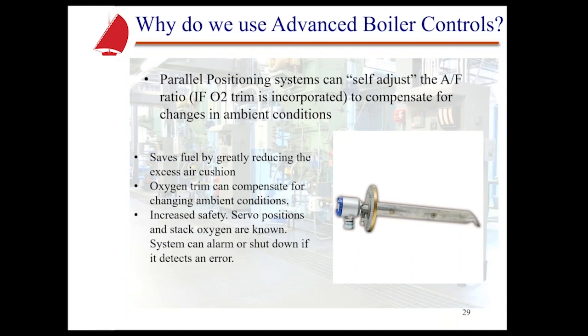So this gives us the capability to adjust beyond just those positions. We're going to make sure that it gets back to what we wanted it to be as it modulates in that firing rate range. It really is the best way of making that system work beyond parallel positioning. And it increases safety. You can set these O2 systems up so that if for some reason we start getting really low O2, something's wrong, and we could either alarm or shut down off of that. So it really does make the system safer. O2 trim is a huge, very popular option.